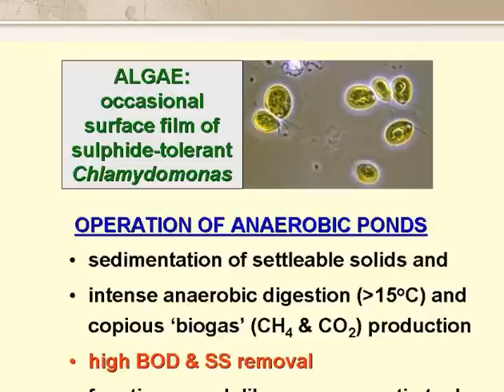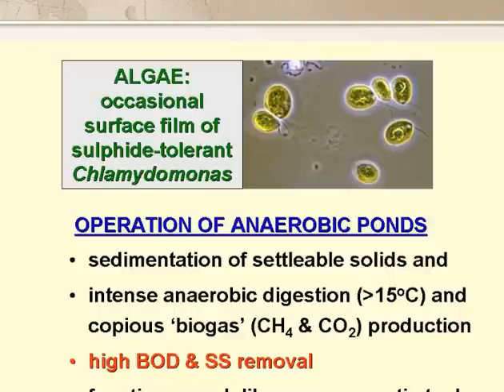The operation of anaerobic ponds is quite straightforward. The settlable solids settle out to form a sludge layer, and especially at temperatures above 15 degrees C, there is intense anaerobic digestion in the sludge layer, and a lot of biogas — methane and carbon dioxide — is produced. In warm climates the removals of BOD and suspended solids are both very high, and in general terms an anaerobic pond functions much like an open septic tank.